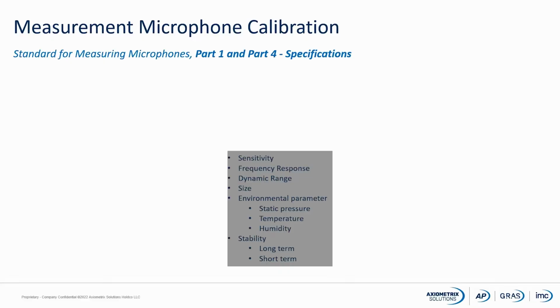Also, stability is described, both long-term stability, how much drift we actually see over time of the microphone, and short-term stability, how fast the microphone is up and running and measuring correctly after you have switched on power to the microphone.